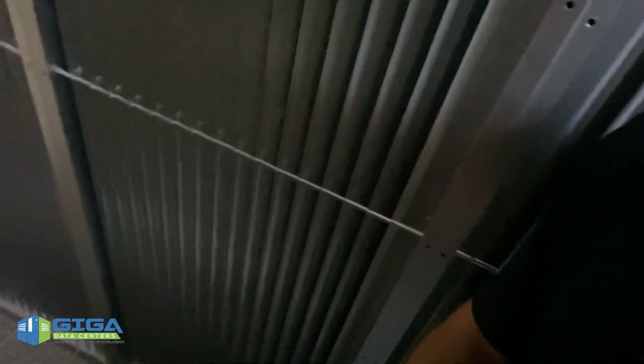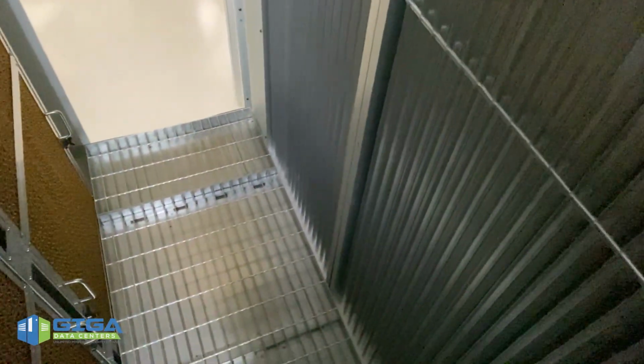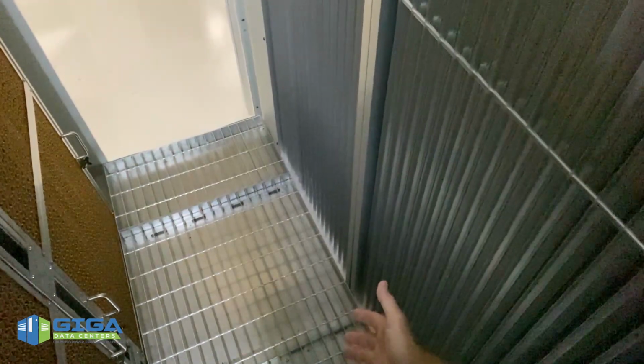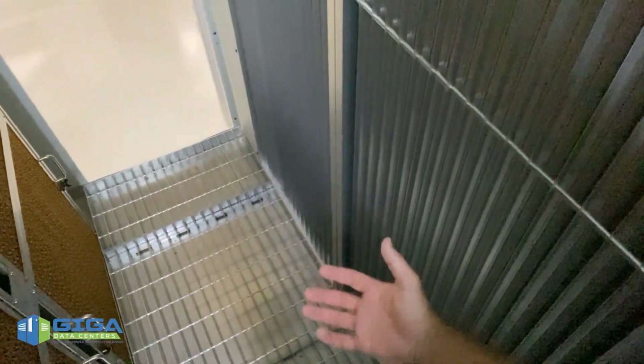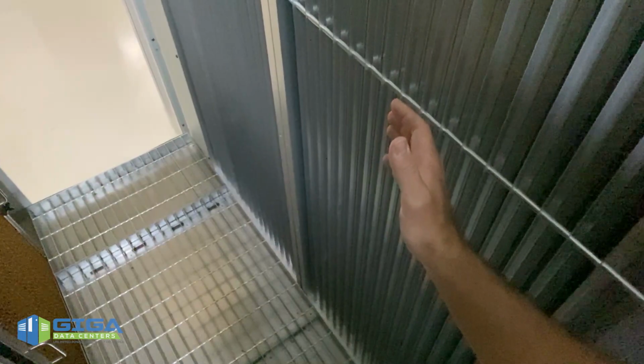This side of the wall here is really to catch any condensation. So if the air moving through this chamber ever has too much humidity in it, that humidity would collect on these metal sheets here, drip down to the bottom. The floor in this chamber of the unit is actually essentially a giant drip pan. So if any solenoid valves were to fail, if too much water were to catch on the condensate sheets and drop to the floor, we would then have the ability to easily remove that water from the unit. So that would never be an issue.